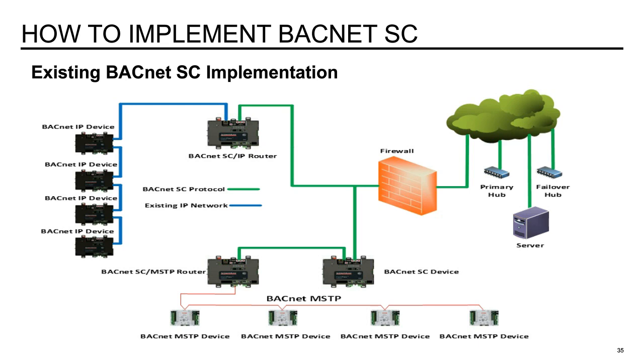So what ends up happening is, in the case of what I have on the screen right now, like I said before, this green is from the firewall to this BACnet SC IP router, and this blue is from the SC IP router to these BACnet IP devices. This would be the customer's existing IP network, if you will, a Cat5 or Cat6 cable, whatever the case may be. You put the BACnet SC IP router in on that network, and then the BACnet IP devices talk to the BACnet SC IP router using BACnet IP, and then the BACnet SC IP router talks BACnet SC back to the hub.